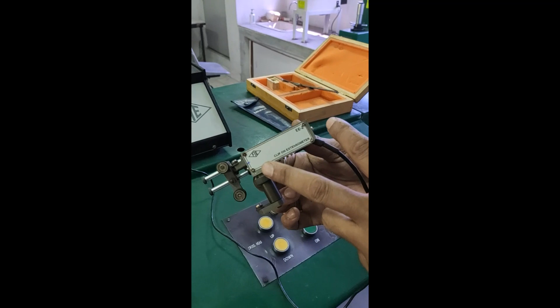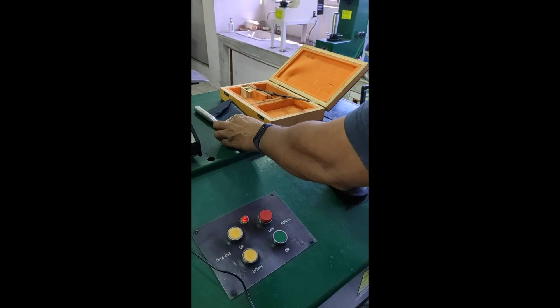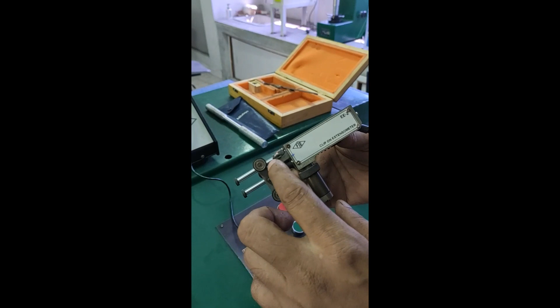So that's why we will not take it up to the failure of the specimen, and we will remove this extensometer in between the test. At what interval we will remove it, we have already set it, generally at 1.5 or 1.8 mm extension of this extensometer. We will take out the extensometer. Why have I chosen 1.5 mm or 1.8 mm of extension for removal of this extensometer?